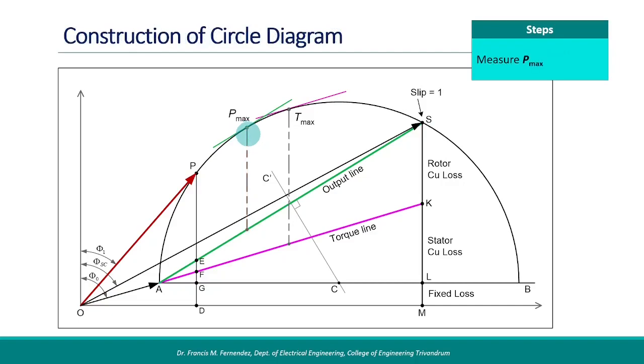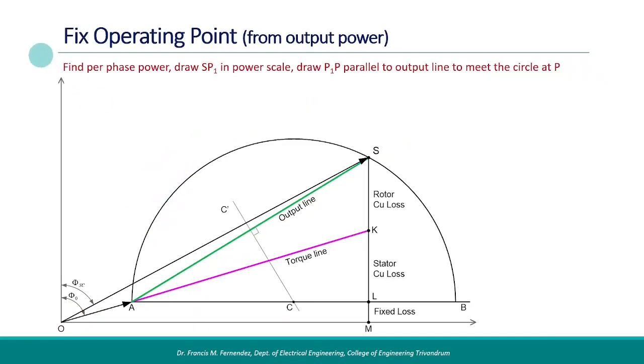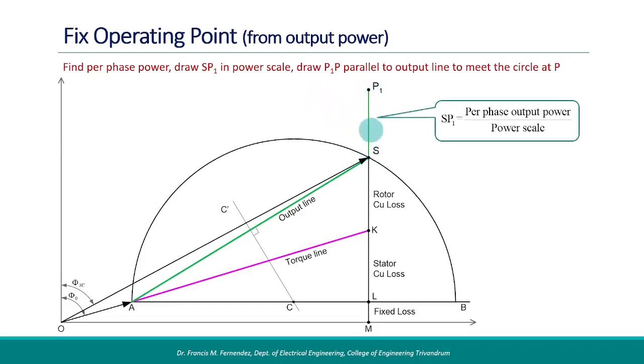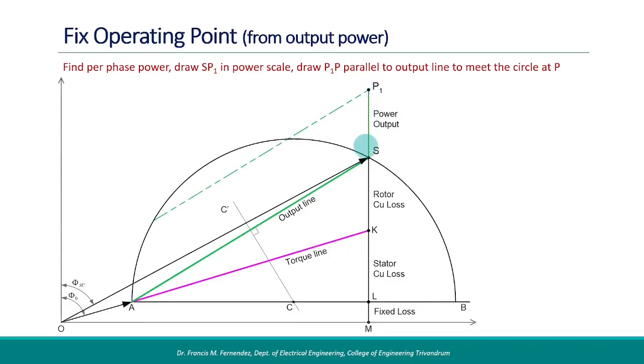In the procedure seen so far, the operating point is fixed based on the input current. If the operating point is to be fixed based on the output power, find the per-phase power output and convert it to an equivalent length sp1 using the power scale. Then draw a line p1p parallel to the power line so that it cuts the circle. It cuts at two points; select the lower side point as the operating point P. Once the operating point is fixed, other parameters can be found using the same procedure as before.